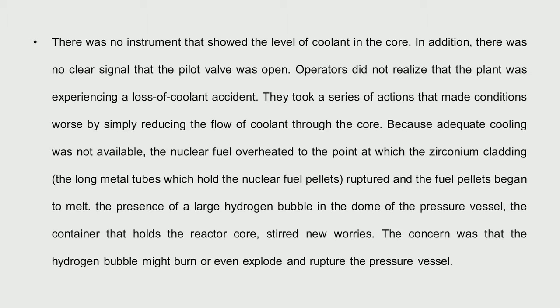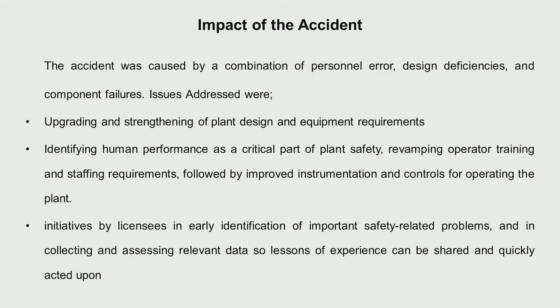The fuel pins ruptured and some of the fuel pellets melted. The hydrogen generated due to the reaction of the zirconium clad with water came out. Luckily, nothing happened — it didn't reach explosion levels. Effectively, there were design deficiencies: no proper instrumentation signals were available to the operator to assess the state of the plant. There was also personnel error in the sense that the operating personnel could have checked other aspects before turning off the cooling to the core, because removing cooling from the core is a very, very important step.